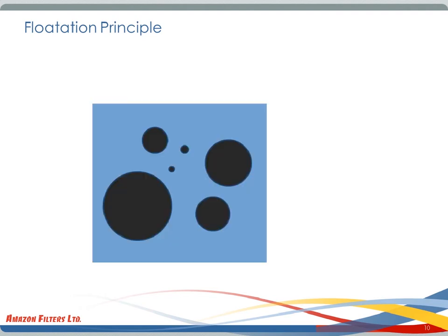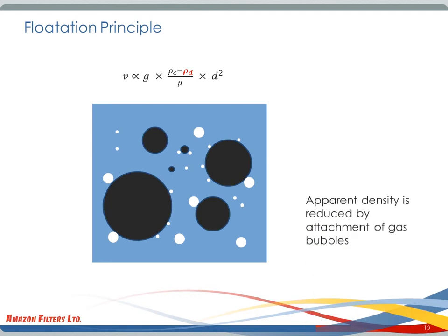The next principle, which is used in dissolved air and induced gas flotation, is the principle of flotation. Here we bubble gas through our produced water, which then becomes attached to the oil droplets.